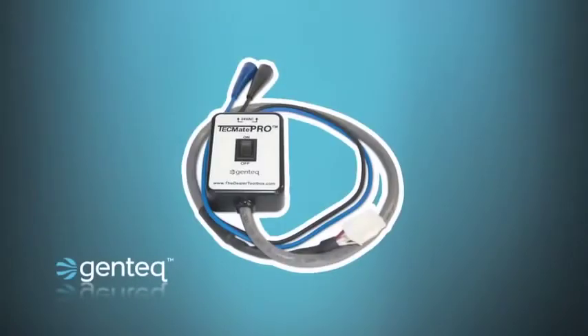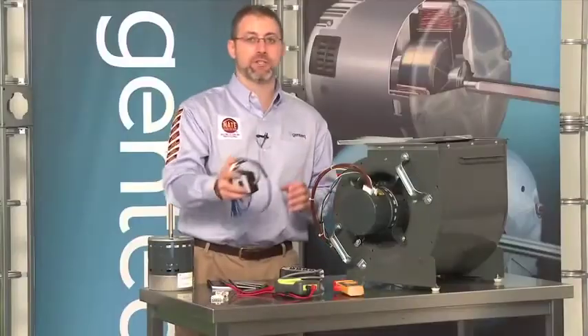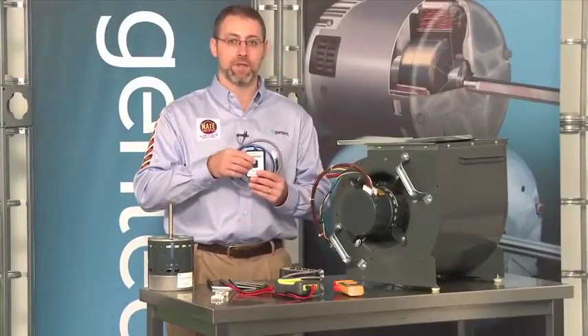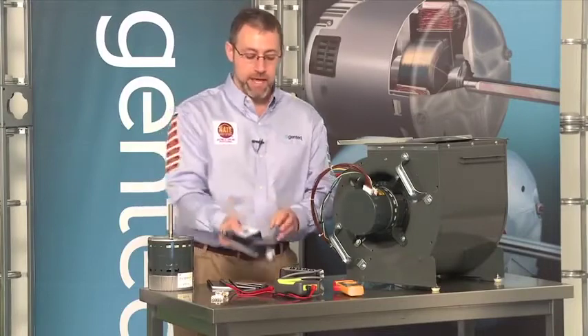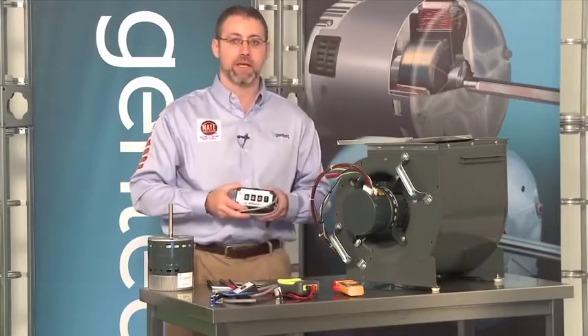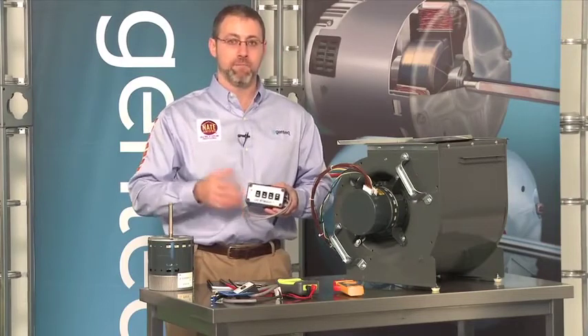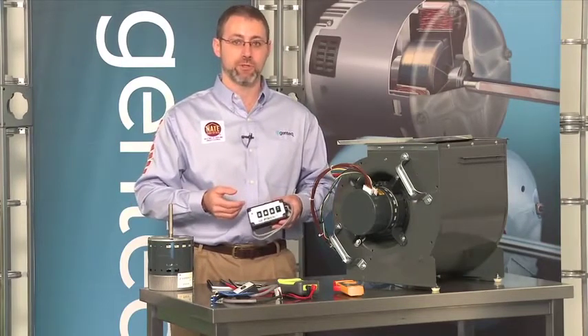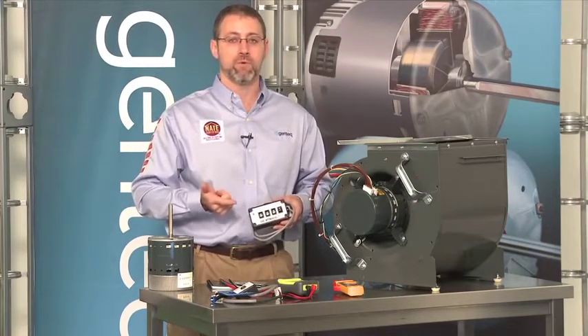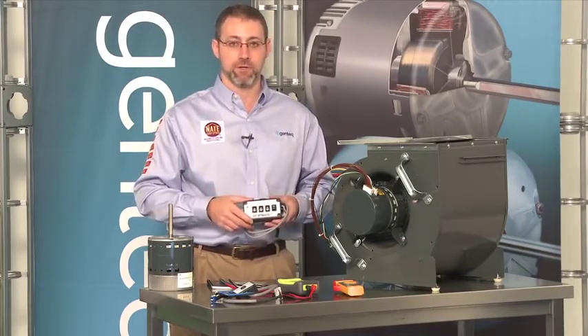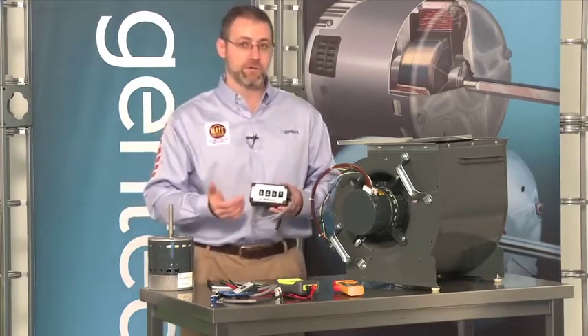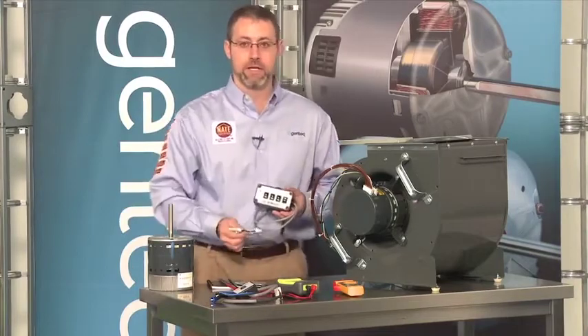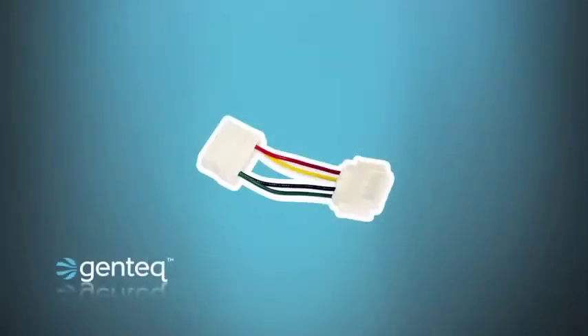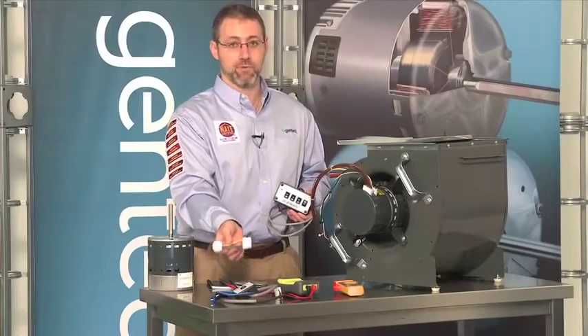The TecMate is the ultimate all-in-one tool when it comes to troubleshooting variable speed motors. The current generation TecMate is the TecMate Pro with a single switch on it. Some of you may have our previous generation, the TecMate XL, with 4 switches on it. Both of these devices will troubleshoot our models 2.0, 2.3, and 3.0 motors. The only thing that's needed for either device to troubleshoot the 3.0 motor is the 16 to 4 pin adapter, which if you buy a TecMate Pro today, comes with the device.